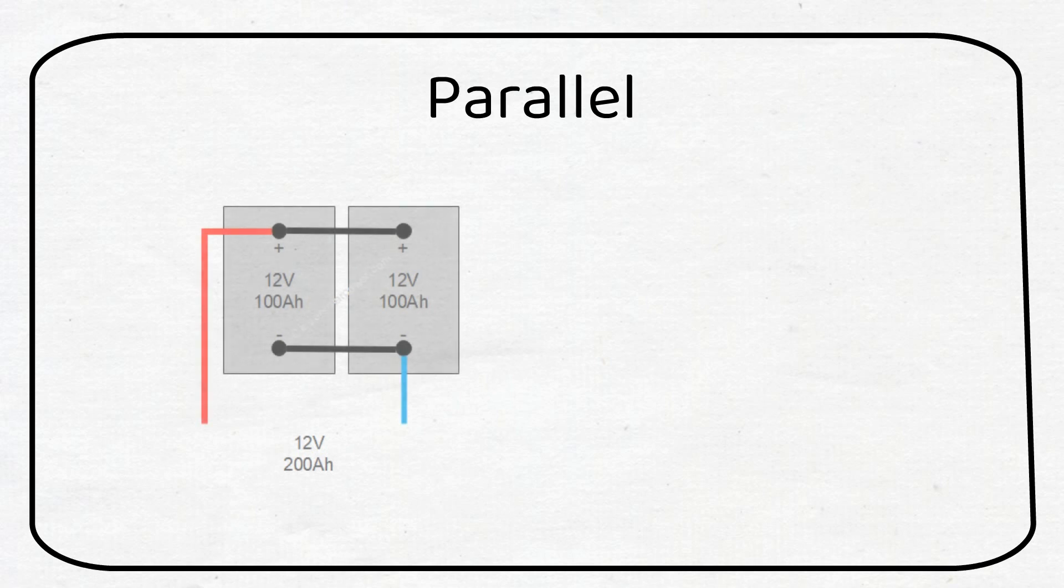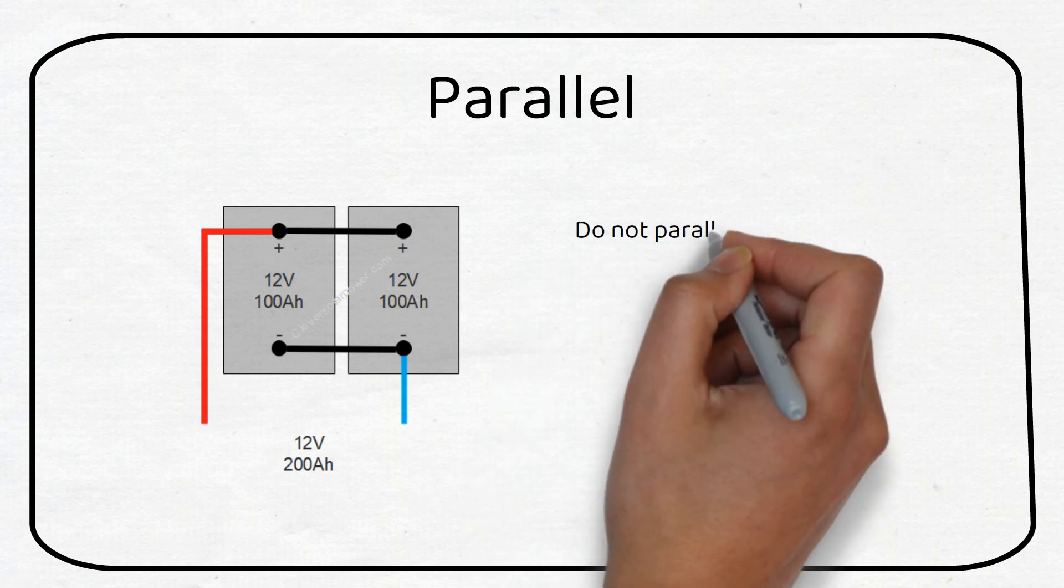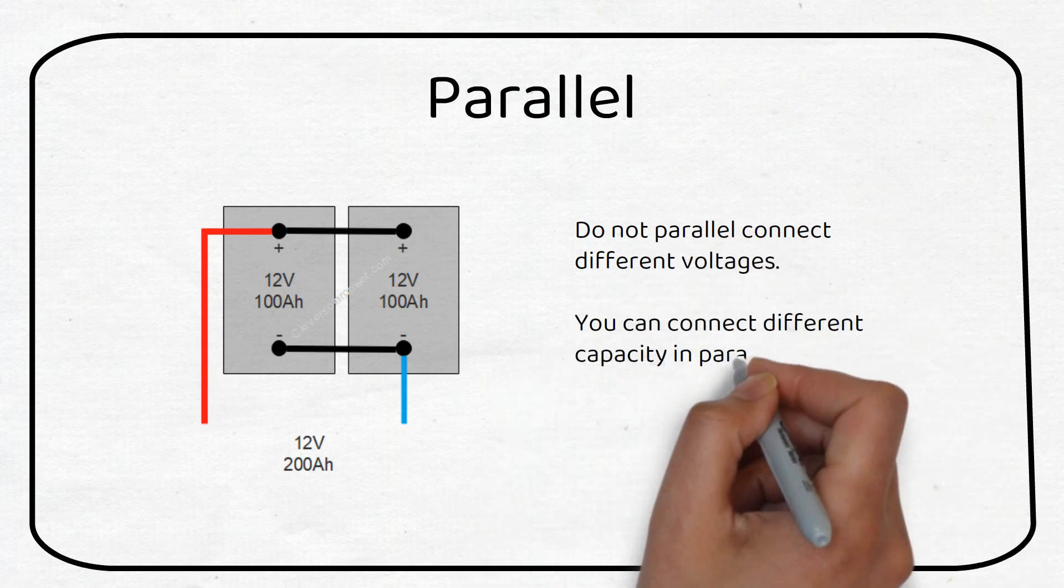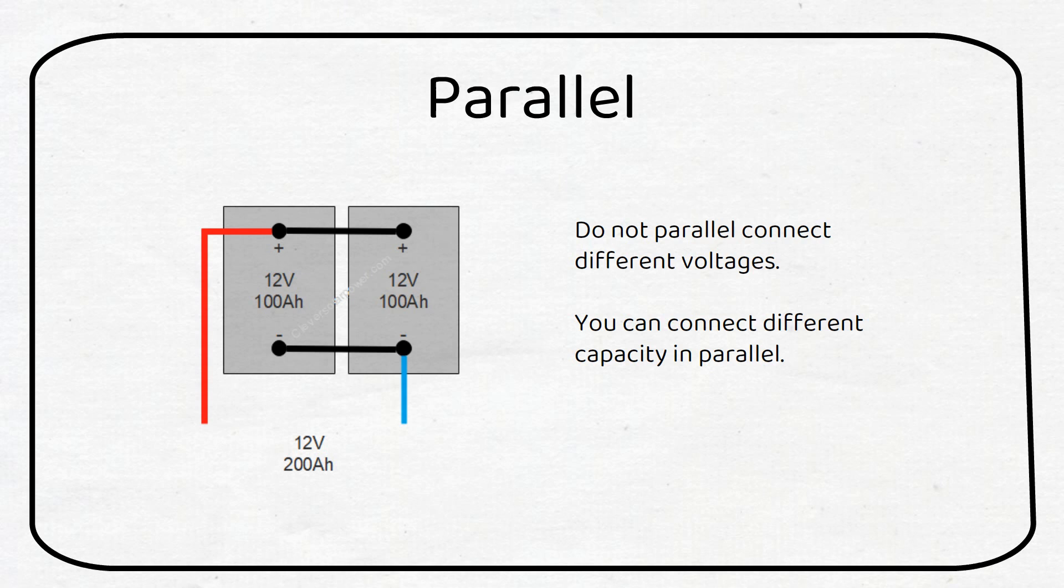If we wire our batteries in parallel the capacity will increase while the voltage stays the same. If we take the same batteries we will have 12 volts and 200 amp hours. Do not parallel connect different voltages. Different capacity batteries can be connected in parallel if they have the same chemistry.